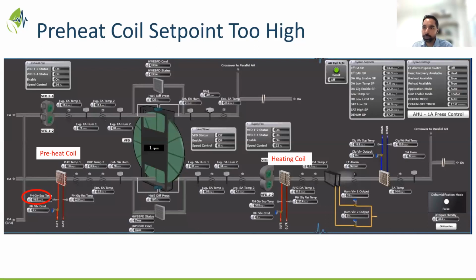However, when you look at the psychrometric analysis and the shop drawings of these wheels, the frost protection doesn't kick in in most of the fields, even close to -15 degrees C. In certain cases, they have even recommended going below -15 degrees C as well. There are many facilities currently running preheat coil temperatures below or close to -15 degrees C, which includes hospitals in Alberta and Ontario. So it is a safe operation in the majority of climate weather.